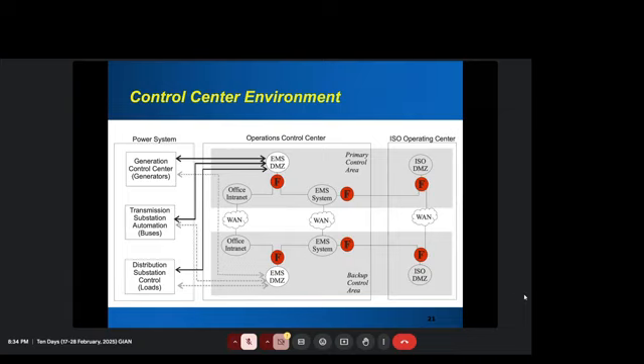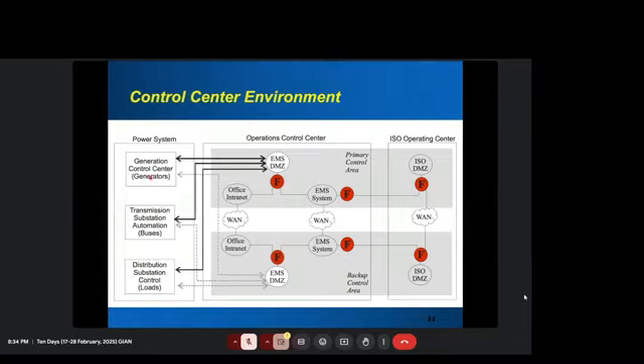So this is a typical architecture. If you look at this system, you have the generation control center, we talked about nuclear, then transmission, then distribution. Then you have multiple firewalls: one is the operation control center, and one is the ISO operation control center. The ISO gets all the data to analyze, but has no control, because they're like a secondary higher authority over the utility control center.